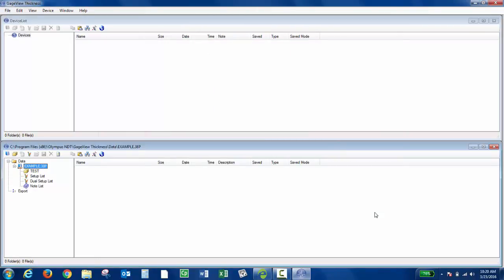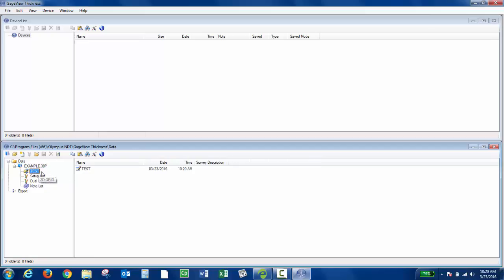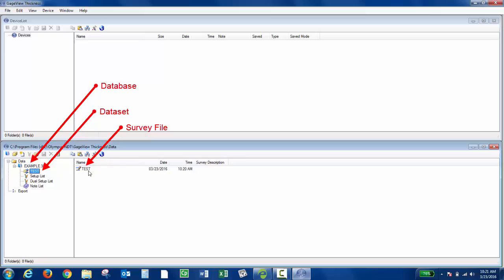So the survey file will automatically be created in GageView and can be sent to a thickness gauge. So here's my data set, if I click that just once. So that's actually what gets transferred to the instrument and is read by the instrument. So from here I could initialize my thickness gauge and actually take the survey file, that test with the pencil and paper icon next to it, and transfer it to the instrument.